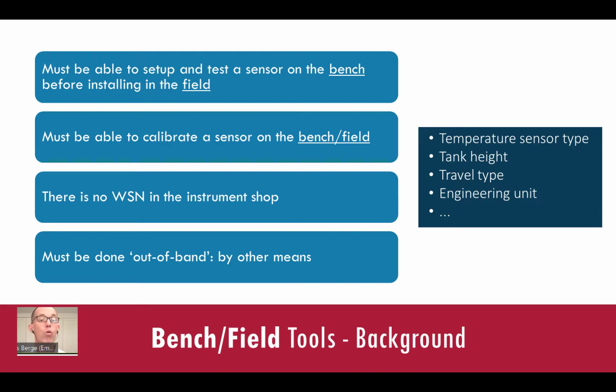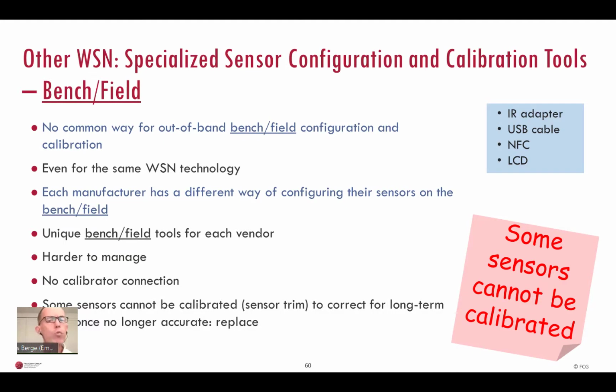Since there is no wireless sensor network in the instrument shop, there must be an easy way to do this by other means. For several wireless sensor network technologies, there is no common way for bench or field configuration and calibration. That is, even for the same technology, manufacturers have different ways of configuring the sensor on the bench before it is brought into the field. This means different specialized tools for each vendor.